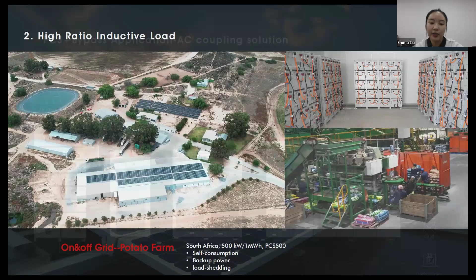Another important pain point of the large-scale project is its high-ratio inductive load. Here are some pictures of the potato farm project we have done in South Africa. There are water pumps and heavy machines for packaging, and the inductive load power is more than 70%. The problem is when the grid is off, when the system needs to switch from on to off-grid working mode, AC output fluctuations caused by switching can endanger system stability.